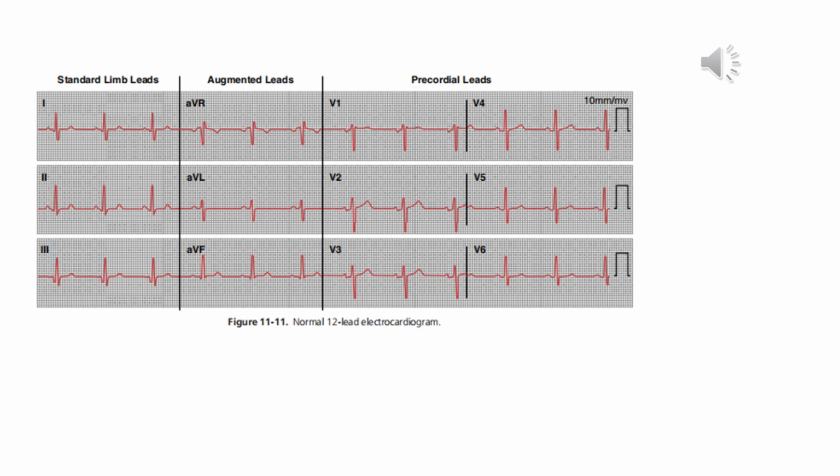These devices can also be used to detect asymptomatic cardiac arrhythmias such as atrial fibrillation that may increase the risk of embolus formation, which can, in turn, cause strokes. Because the daily variability in the frequency of arrhythmia is substantial, detection often requires ambulatory electrocardiographic monitoring throughout the day. There are several categories of ambulatory electrocardiographic recorders. Continuous recorders, Holter monitors, are typically used for 24 to 48 hours to investigate the relationship of symptoms and electrocardiographic events that are likely to occur within that time frame.